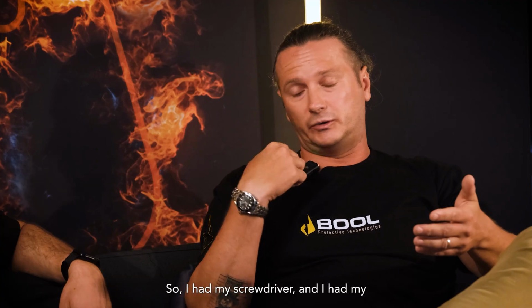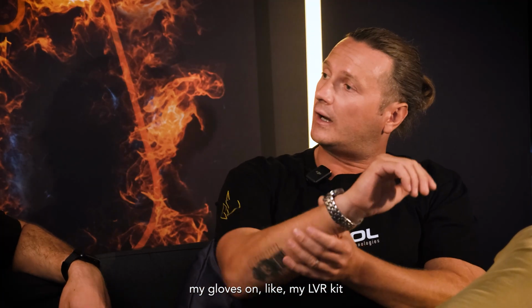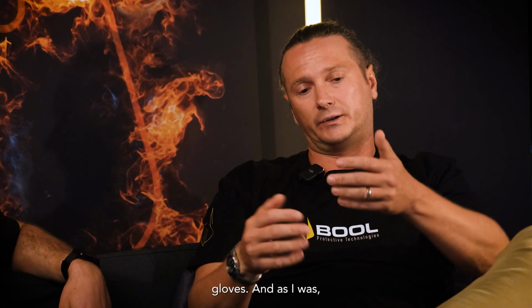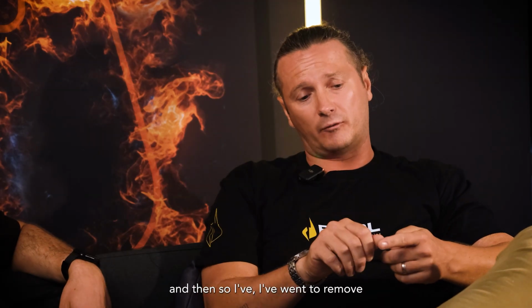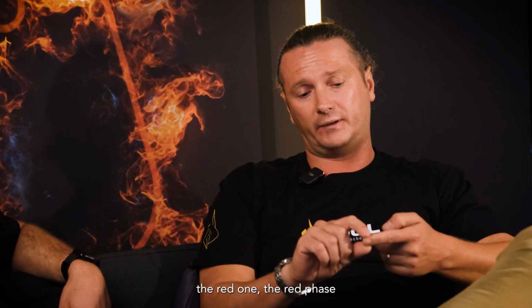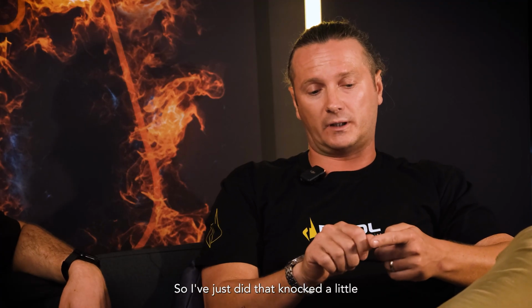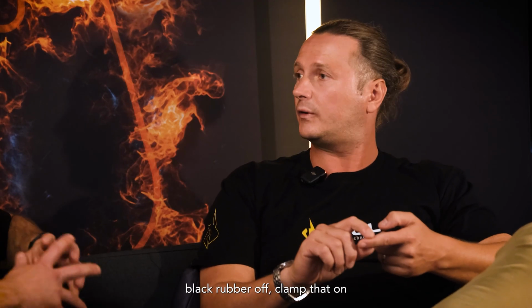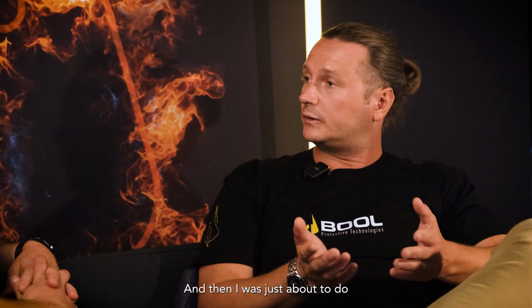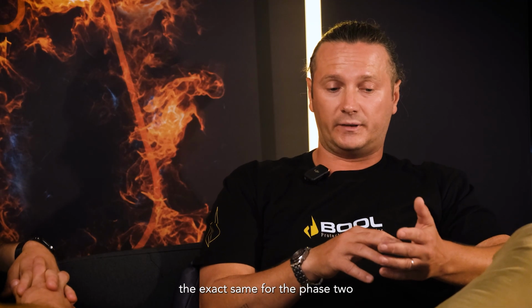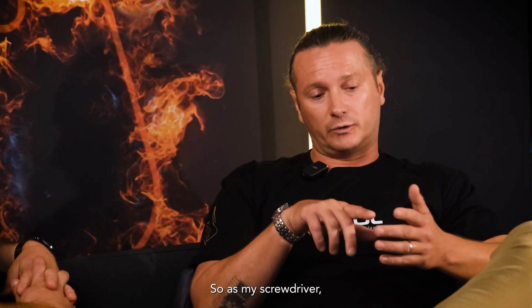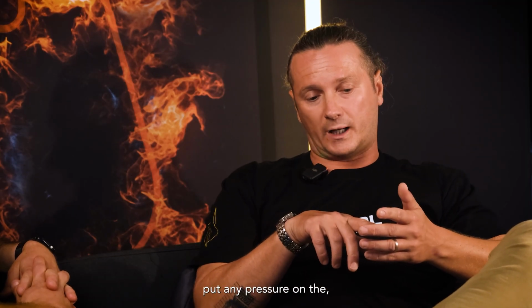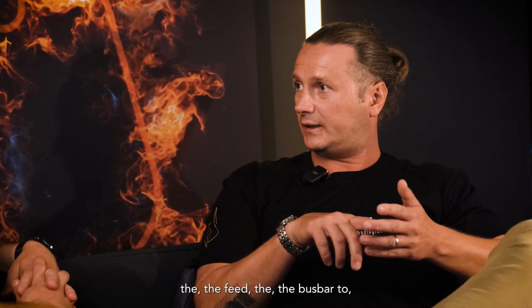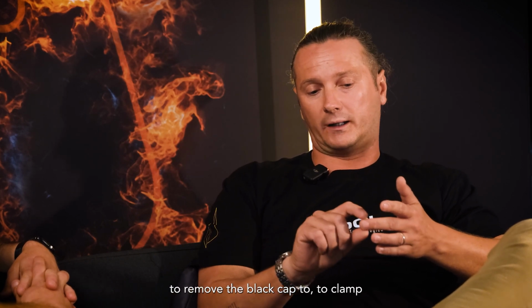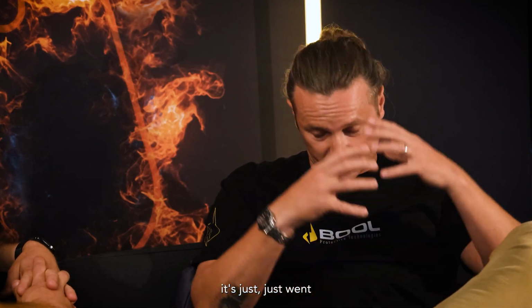So I had my screwdriver, and I had my gloves on, my LVR kit, inners and outers. I went to remove the red one, the red phase, to get the crocodile clamp on. I just took the little black rubber off and clamped that on. Then I was doing the exact same for phase 2, the white phase. As soon as I put any pressure on the phase, the busbar, to remove the black cap to clamp, as soon as I touched that, it just went.